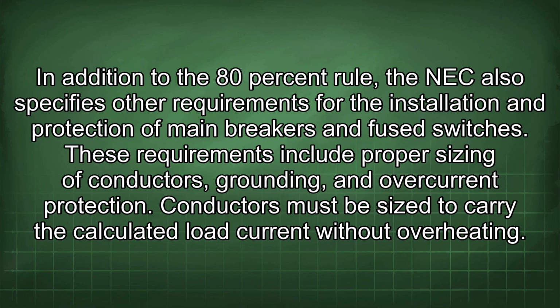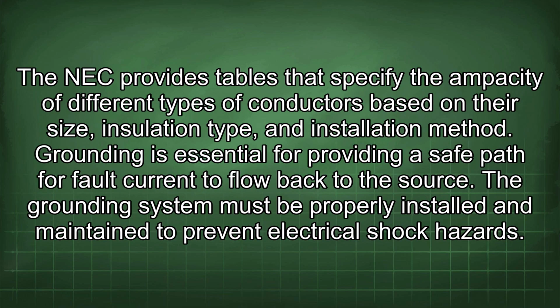In addition to the 80% rule, the NEC also specifies other requirements for the installation and protection of main breakers and fuse switches. These requirements include proper sizing of conductors, grounding, and overcurrent protection. Conductors must be sized to carry the calculated load current without overheating. The NEC provides tables that specify the ampacity of different types of conductors based on their size, insulation type, and installation method.